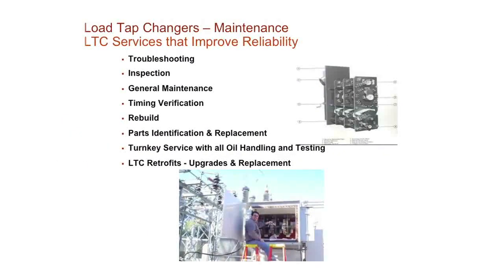The products we support are ABB, Reinhausen, GE, Westinghouse, Allis-Chalmers, and Federal Pacific. If you have a problem unit, you can always look at an LTC retrofit. In a lot of cases, a retrofit solves the problem of an older existing LTC that may be beyond its useful life. We talked about procuring new or better parts, and we'll supply the parts, or we can supply the parts and the LTC technician, depending on what's needed. We can handle the oil, or we can have the customer handle the oil. We're pretty flexible in that regard.